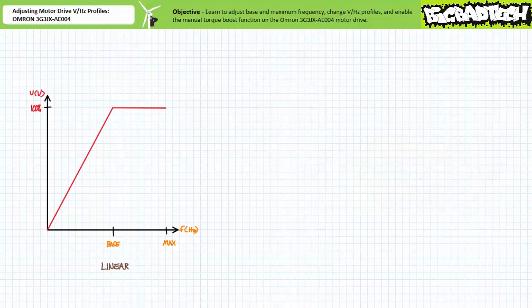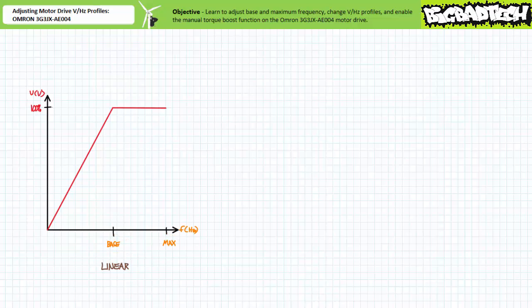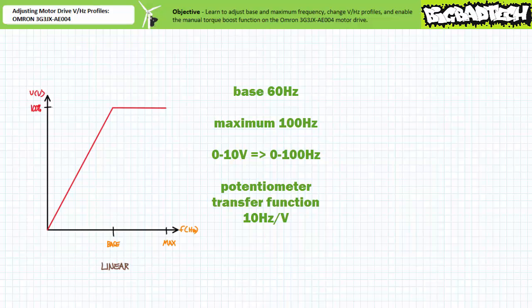Really there are only two key data points that define the simple linear volts per hertz profile: namely base frequency entry A003 and maximum frequency A004. From zero to base frequency, applied voltage is linearly proportional. Beyond base up to maximum frequency, applied voltage flat lines at 100 percent. When base is 60 hertz and the maximum is 100 hertz, note the external speed potentiometer's zero to 10 volt analog voltage input is scaled to represent the zero to 100 hertz range.